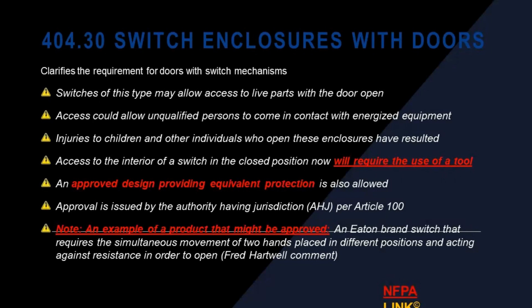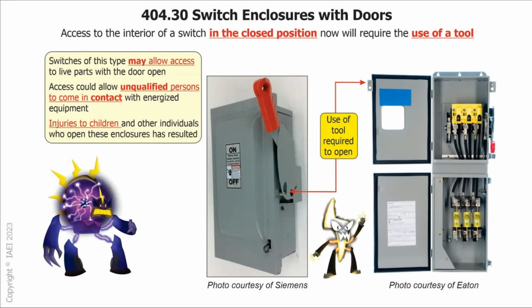404.30, switch enclosures with doors. Switches of this type may allow access to live parts when the doors open. Access to an interior of a switch in the closed position will now require the use of a tool. An approved design providing equivalent protection is also allowed. An example of a product that might be approved is the Eaton brand switch that requires simultaneous movement of two hands placed in different positions and acting against resistance in order to open. Okay, so there's a couple of ways to do this, but from now on, our little one-arm bandits and stuff, they're going to require the use of a tool to open them, especially if they allow access to live parts. That's the point of that one.